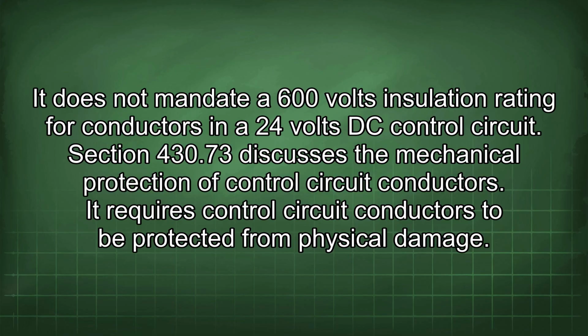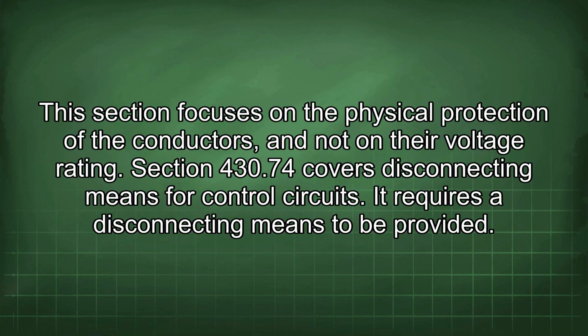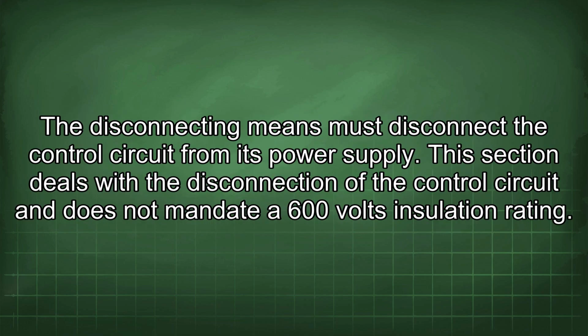Section 430.73 discusses the mechanical protection of control circuit conductors. It requires control circuit conductors to be protected from physical damage. This section focuses on the physical protection of the conductors and not on their voltage rating. Section 430.74 covers disconnecting means for control circuits. It requires a disconnecting means to be provided. The disconnecting means must disconnect the control circuit from its power supply. This section deals with the disconnection of the control circuit and does not mandate a 600 volt insulation rating.